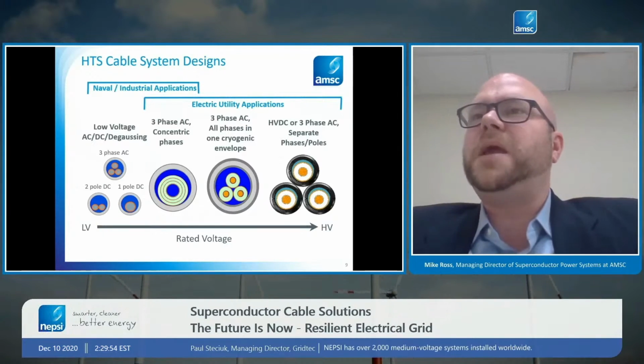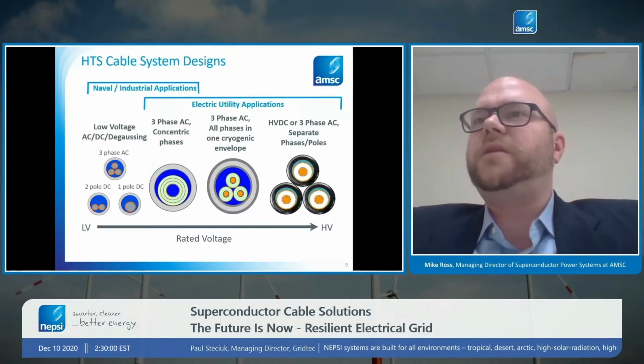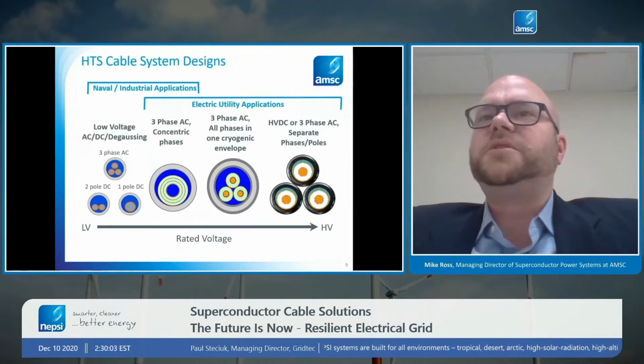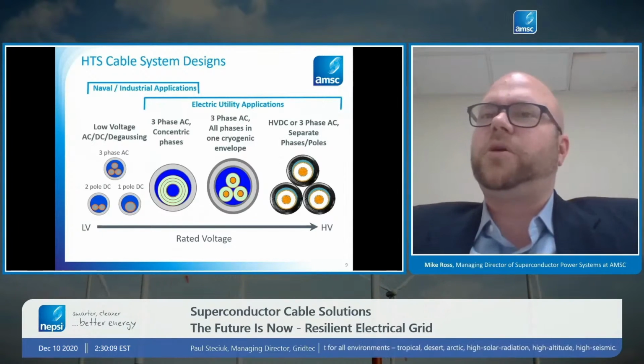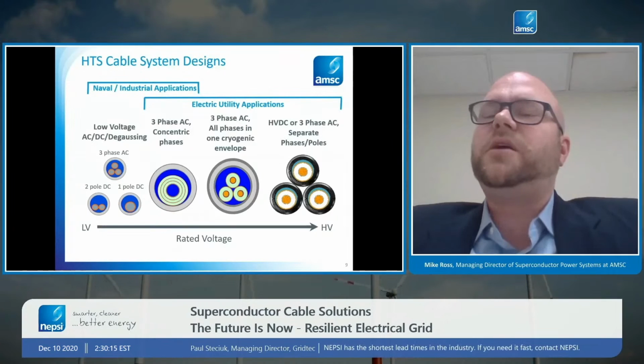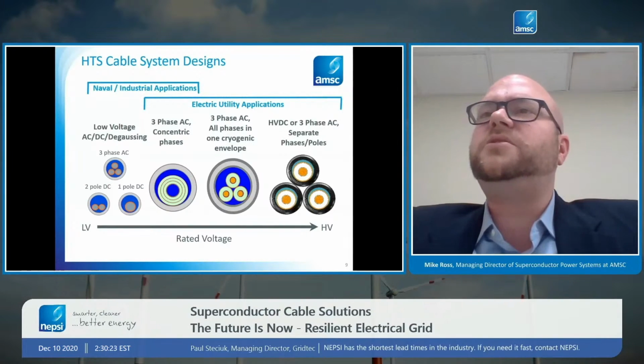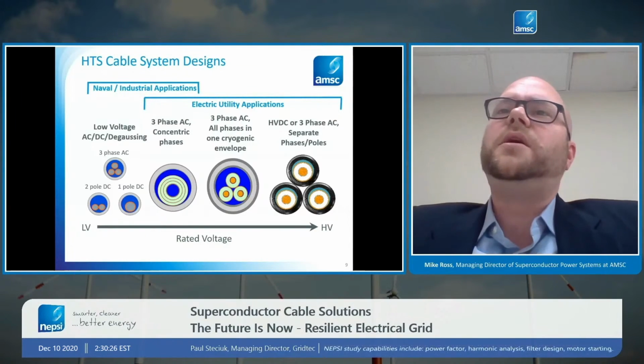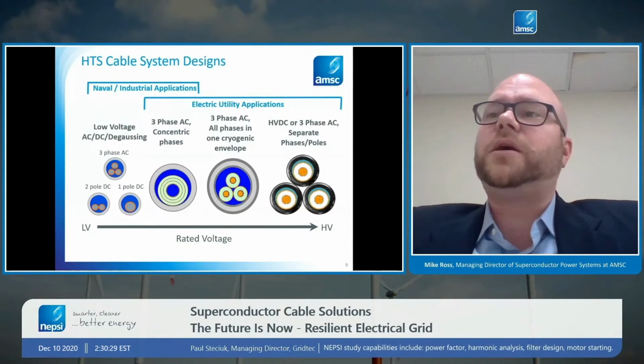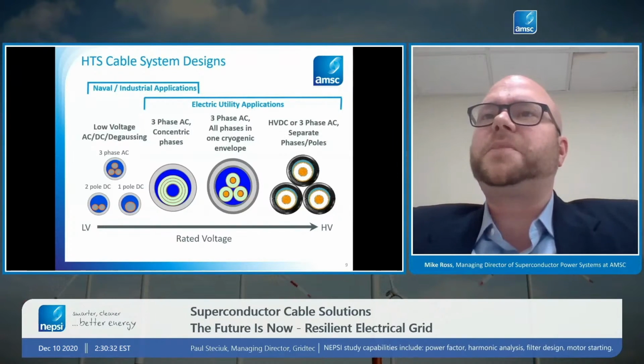This slide is showing the main configurations of superconductor cables. At AMSC, we supply a wide variety of cables. On the low voltage side, we have a variety of cables that can operate at 1,000 volts or below for industrial applications and military applications. So we have three-phase AC cables. Those can be used in places that are using high current AC. There are facilities that use 120 volt or 480 volt AC at very high currents: aluminum smelting, water treatment, water desalination, and many other industries use very, very high current, low voltage cables.